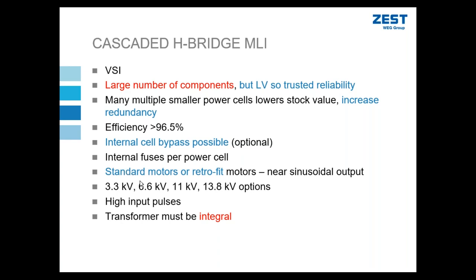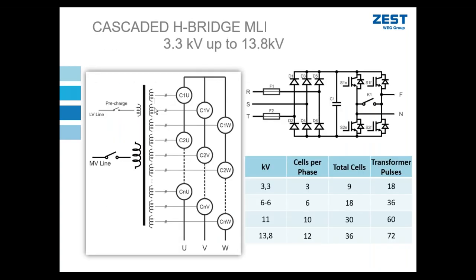Yeah, you do need fuses. Because we are dividing the power into smaller isolated secondaries, I could potentially have an overcurrent or short circuit or fault on one of these power cells. Because it is only a 690 volt isolated supply, it may be too small a current to cause the upstream circuit breaker to trip. That's why I need more localized protection, and that's why I have to incorporate fuses on this topology.